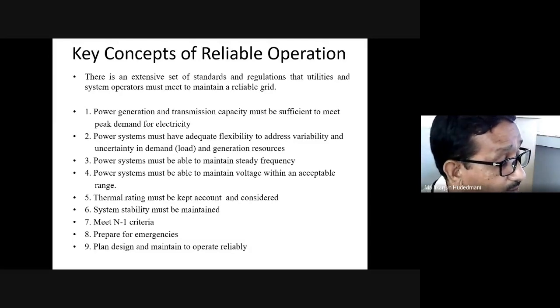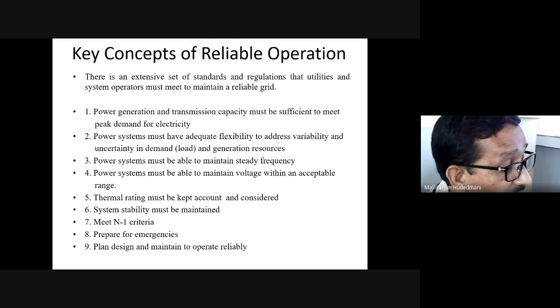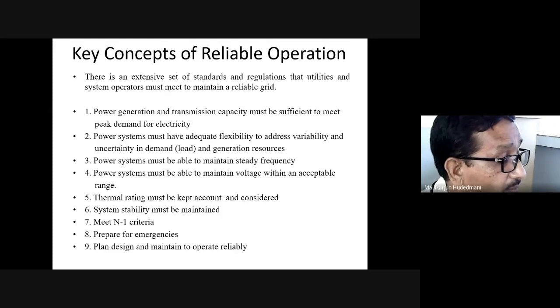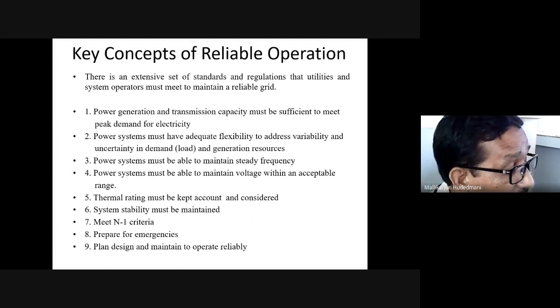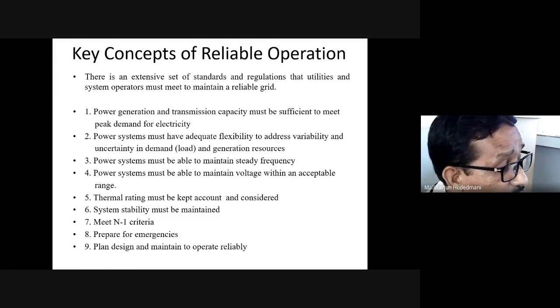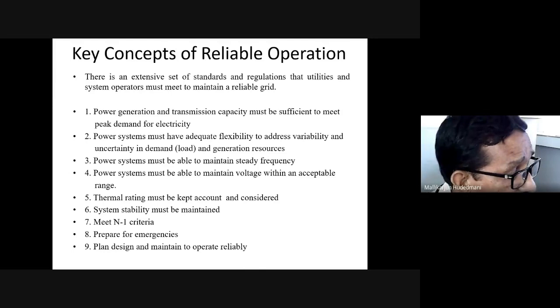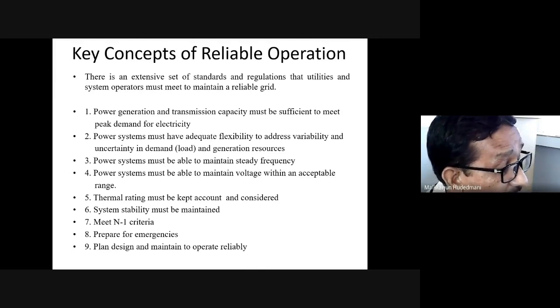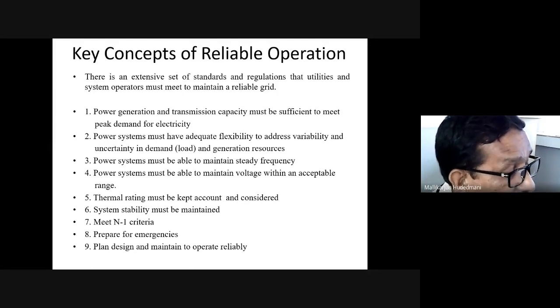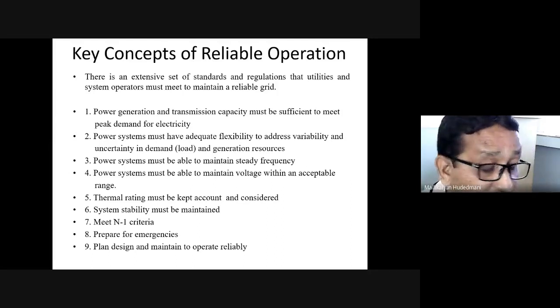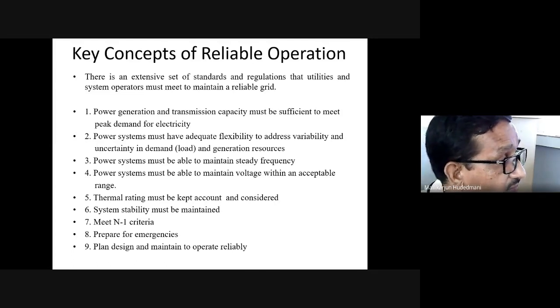Then during that situation, how is the rest of the system, minus the one which is out, going to behave? During such a situation, which lines are getting burdened additionally to deliver the power alternatively via the next route, or the next possible path of the shortest possible? In that regard, the N-1 criterion is very sensible. If any one of the crucial components in the system fails, then the behavior must be such that the system is able to cope up even after the loss of that.